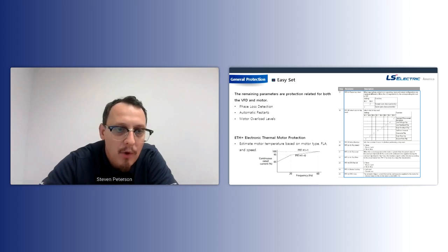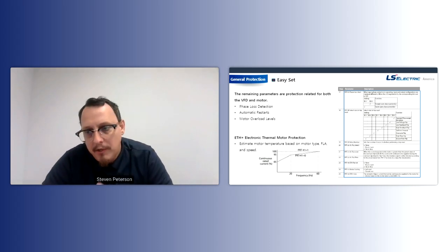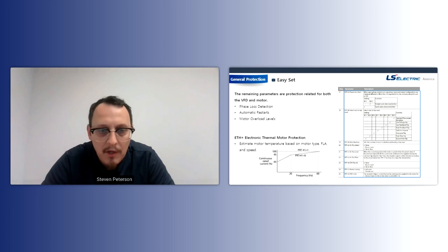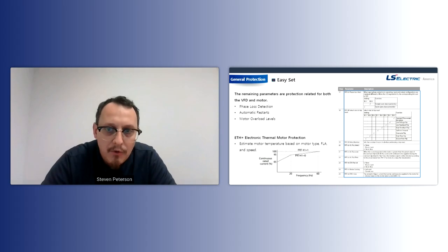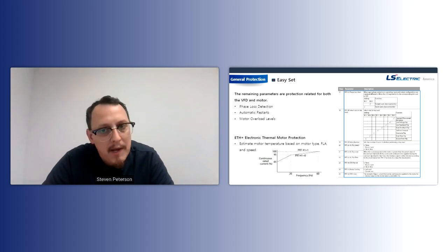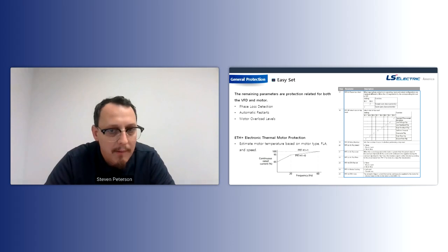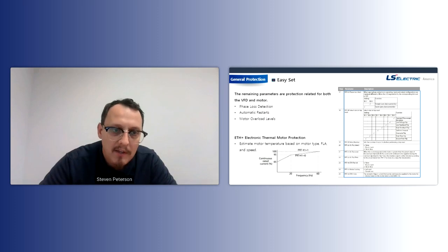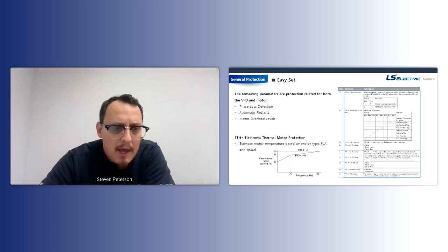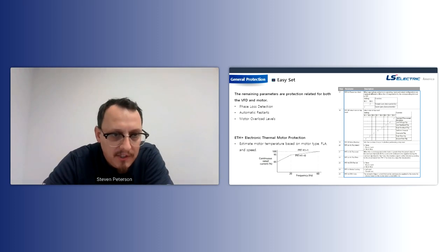And you could also pick out what kind of trips you want to do a reset on. There's standard trips such as motor overload, overcurrent, etc. There's low voltage trips you can enable. And then since this is a pumping drive, you could do automatic reset on a low feedback, a high feedback, set point timeout, overcycling, high flow, a flow accumulation. So there's all these checkboxes on the right here. So you can actually pick what you want the drive to do an automatic restart on based on what type of trip occurs. And the last thing on this slide is just ETH.